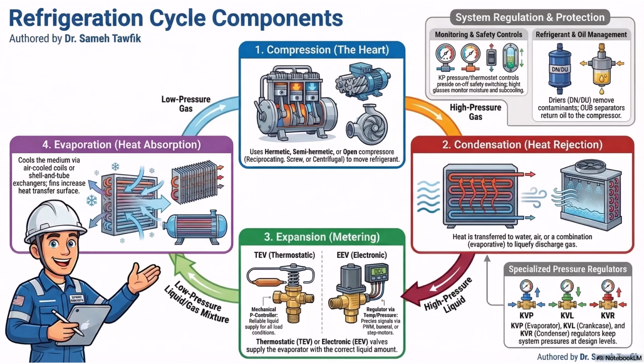Sure. When we looked at the expansion valve earlier, we established its entire purpose is to strictly control the flow and pressure entering the evaporator. So why does the syllabus list half a dozen other pressure regulators? I mean, if the TEV is doing its job, aren't all these other valves totally redundant? What's fascinating here is that they aren't redundant at all.